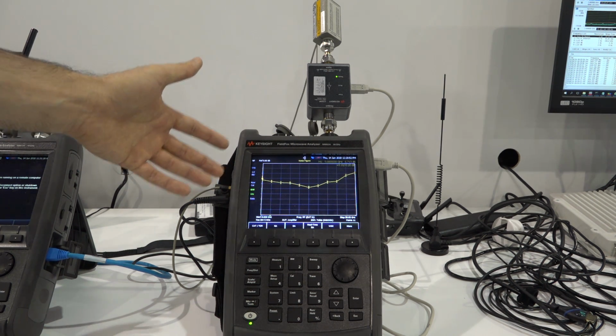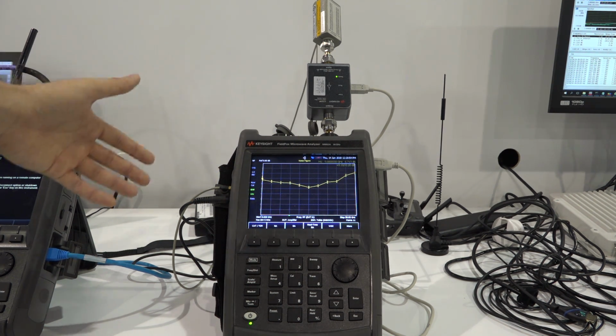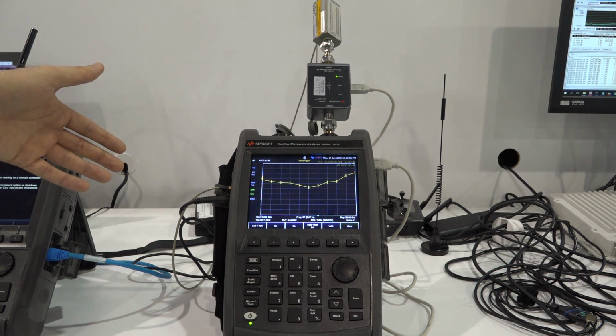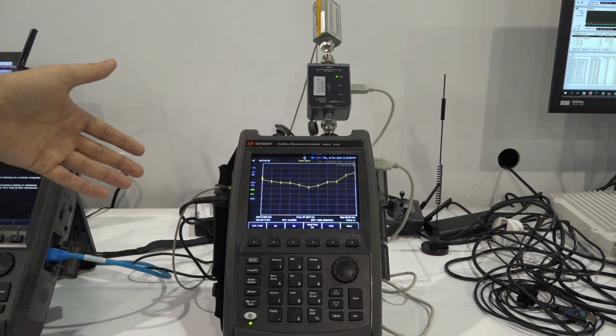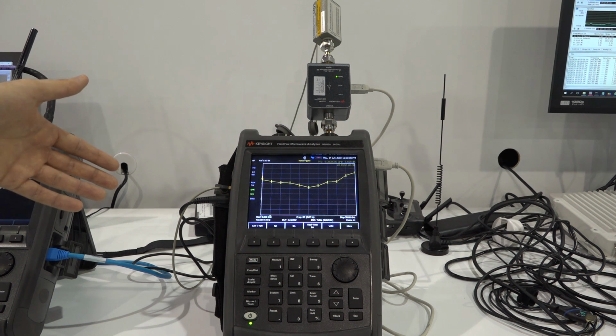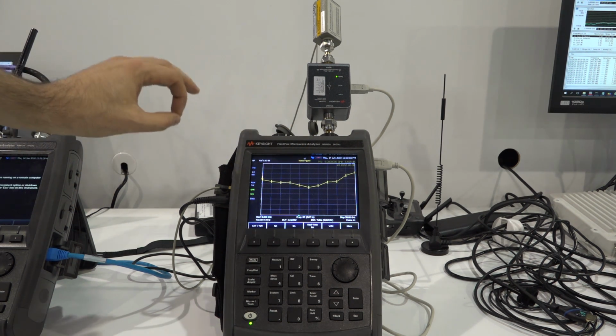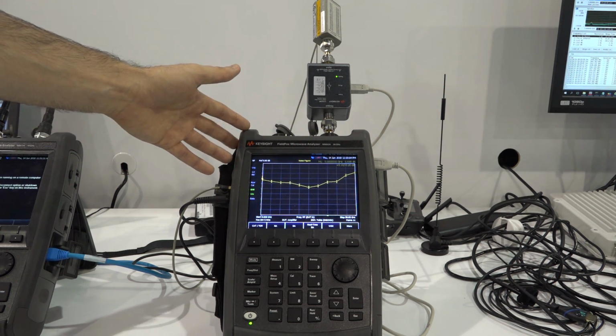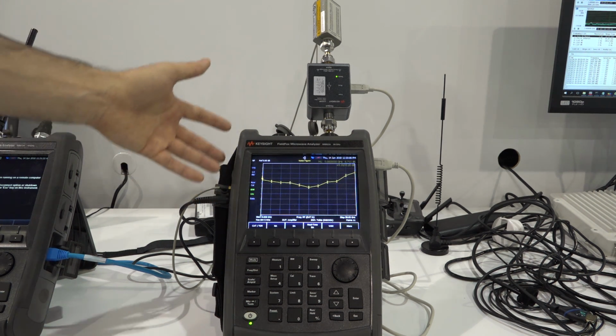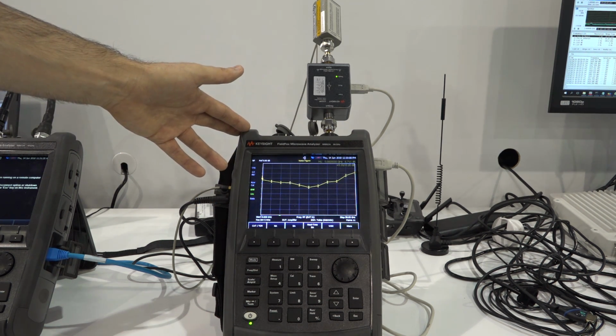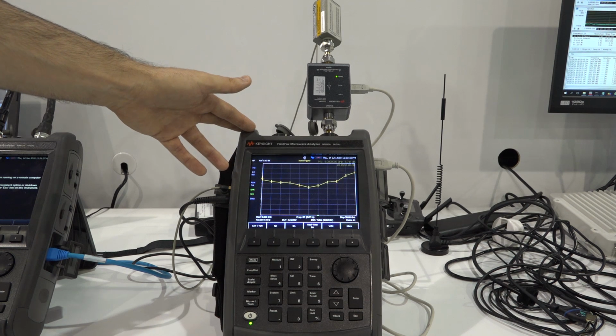And this gives you an uncertainty of your noise figure, depending on whatever parameter is changing in the noise figure measurement itself, ENR uncertainty or any mismatch uncertainty. You can get these bars in real time as you're doing your measurements, which is of course huge, because you need to know if you can rely on this measurement you're getting, especially in the field where time is really important.